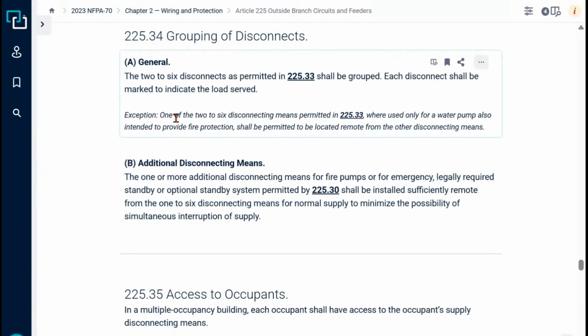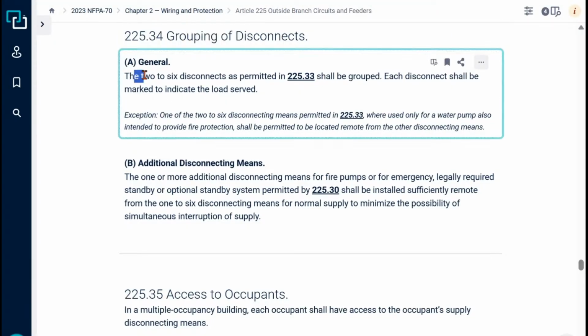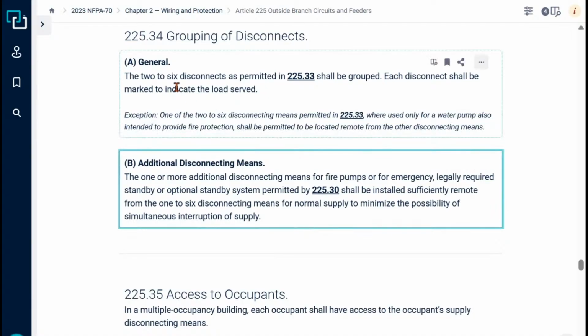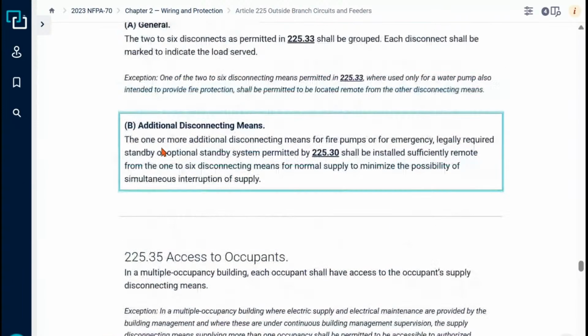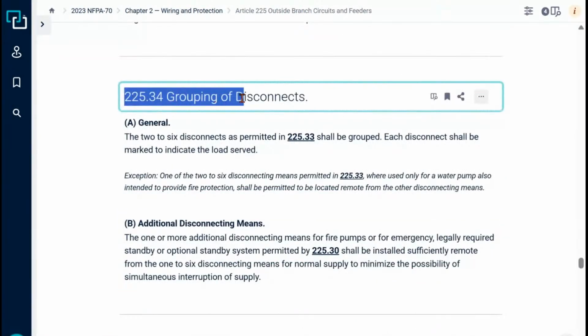You didn't give us enough information on whether we're talking services or feeders. In a feeder application, grouping of disconnects, 2 to 6 disconnects as permitted in 225.33, shall be grouped. Each disconnect shall be marked to indicate the load served. There's an exception for this specific application. So they have to be grouped, but we don't define what grouping is in the code. We just know they're in close proximity. It very much mirrors the same language you'd see in reference to 230.72. Very similar type of application.